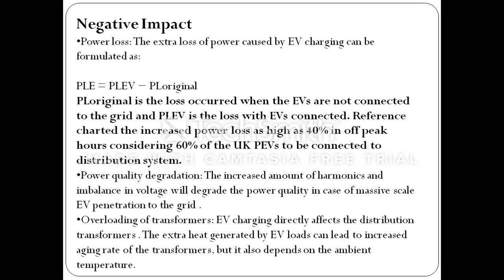Next is overloading of transformer. EV charging directly affects the distribution transformer. The extra heat generated by EV load can lead to increased aging rate of transformer, but it also depends on ambient temperature. So that is overloading of transformer.